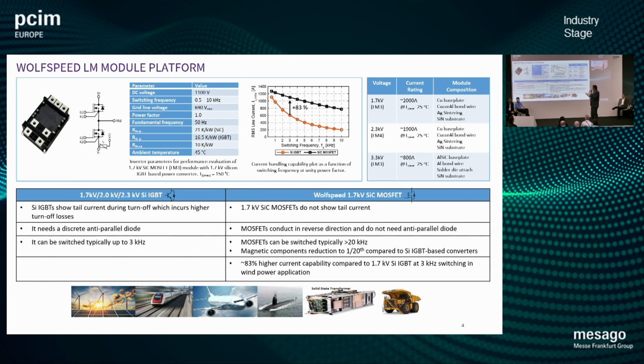But the important thing here is, think of an IGBT, that's the baseline system. It's working its hardest at 800 hertz to 1000 hertz, 1 kilohertz, it's switching capable. When you migrate to silicon carbide, you're not turning a motor. In a solar application, for example, it's a static power conversion. If you're charging a megawatt battery, you can increase that switching frequency. There's no dV by dt isolation challenges of motor windings. If you're using an IGBT, you've got to derate massively as you increase that switching frequency.